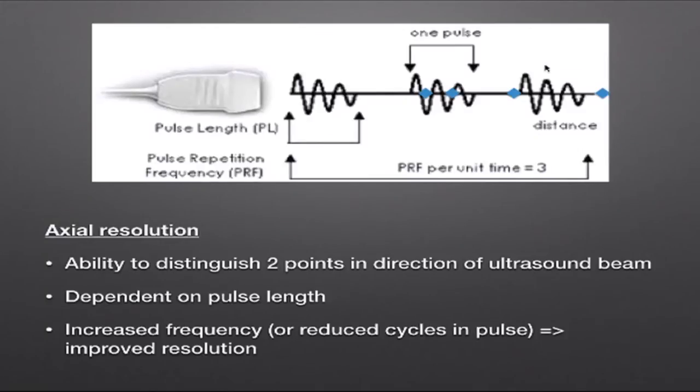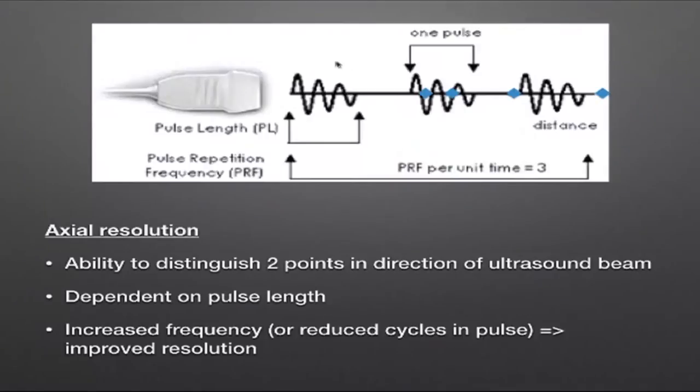Those first two points — closer than the pulse length — cannot be distinguished on the ultrasound image, whereas the second pair can, because they are separated by a greater distance than the pulse length itself. To improve axial resolution, we can either increase the frequency — which reduces wavelength and therefore pulse length — or reduce the number of cycles in the pulse. Both approaches make the overall pulse length smaller, improving the ability to differentiate structures.